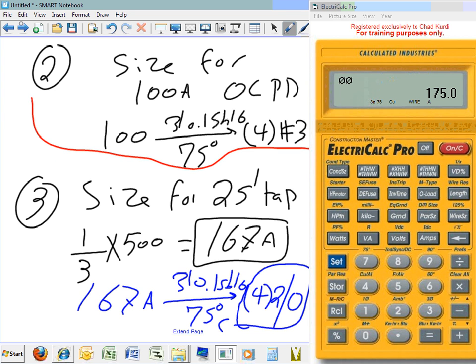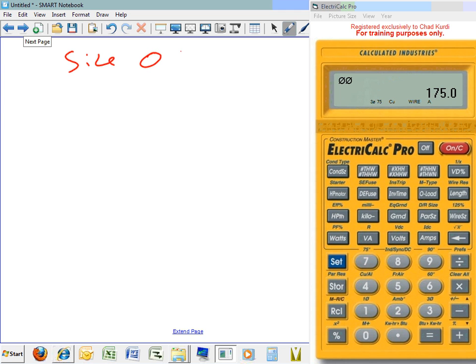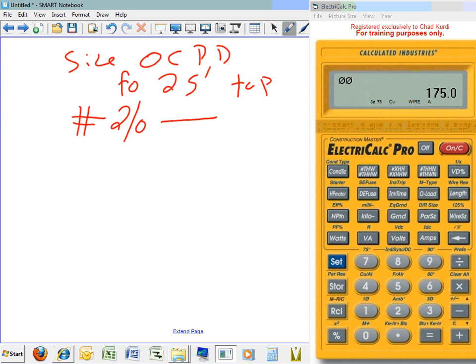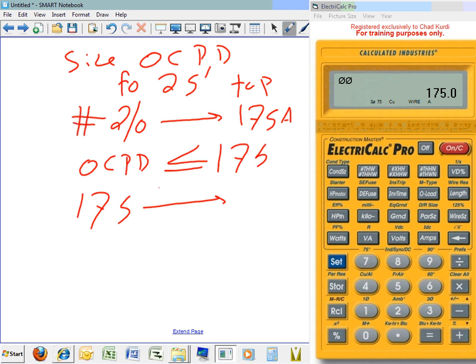All right. There you go, Chad. Okay. Size overcurrent protection device for 25 foot tap. I'm going to remind you guys that the conductor that I use is what? Which number is that? I use number 2 aught. Number 2 aught gave me 175 amps. So my overcurrent device cannot, shall not, will not be more than 175 amps. So my overcurrent protection device must be less than or equal to 175. Okay, so what do you do? You take 175, take it to 240.6 from NEC 2011. What's the next standard? You have to go down, by the way. If it's not a standard, you're going to go down here. So is 175 a standard fuse or circuit breaker?